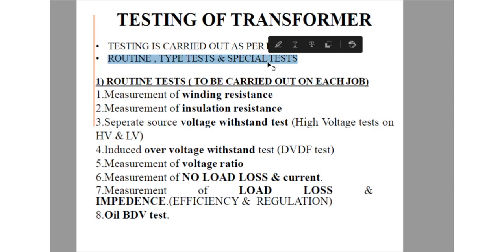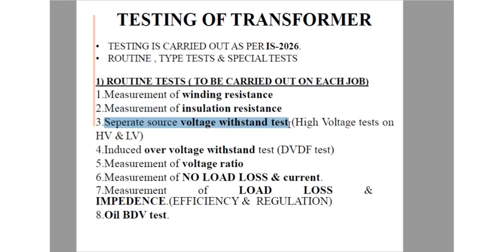Now, what is the meaning of routine test? Routine test means it is to be carried out on each job. We are interested in the measurement of winding resistance, measurement of insulation resistance, and the separate source voltage withstand test. That is called a high voltage test on the high voltage and low voltage side. The fourth routine test is the induced overvoltage withstand test, that is also called the DVDF test.